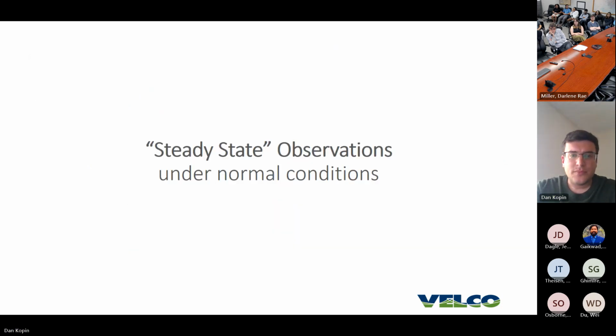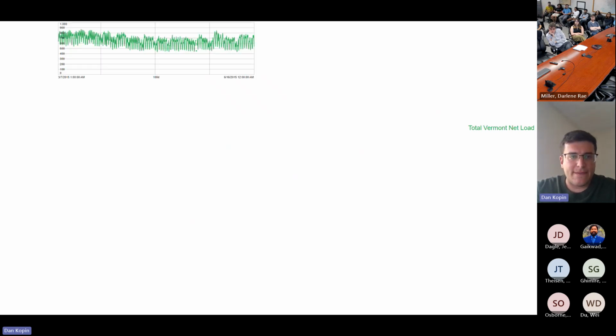Now I'll talk about some steady state observations, meaning normal conditions - that's the basis of what I'll be sharing today. Here's the total Vermont net load from 2015. From March to June 2015, net loads went as low as 450 megawatts, by far the lowest we'd go, while load during that time went up to 900. We're about a gigawatt peaking system historically, so 450 was our lowest at that point.